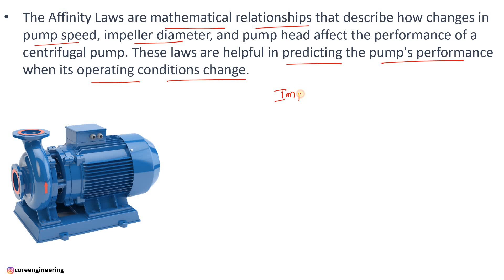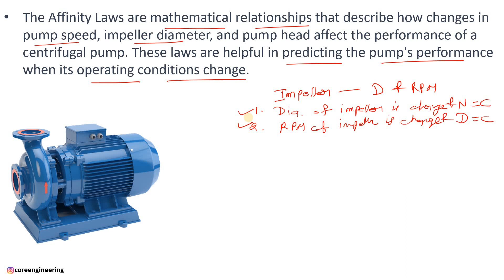There is a relation between the flow rate and the diameter of the impeller, and a relation between the flow and the RPM of the impeller. When these relationships come into the picture, we are going to discuss. As I told you, the centrifugal pump performance depends on the diameter of the impeller and the RPM, so two scenarios come into the picture. The first scenario is that the diameter of the impeller is changed and your RPM is constant. The second scenario is that the RPM of the impeller is changed and the diameter D is constant. Are you getting my point?